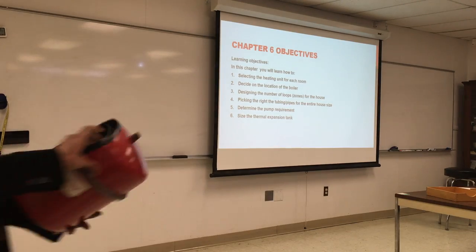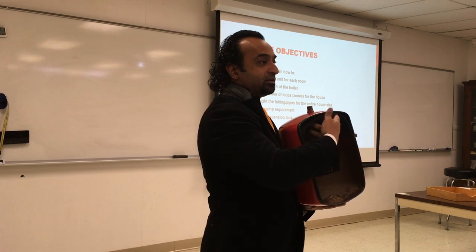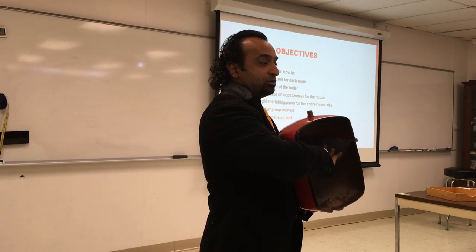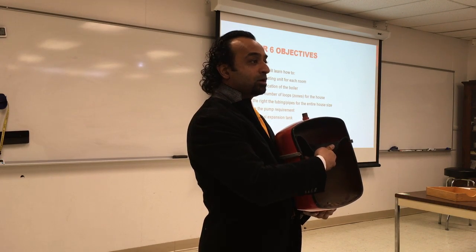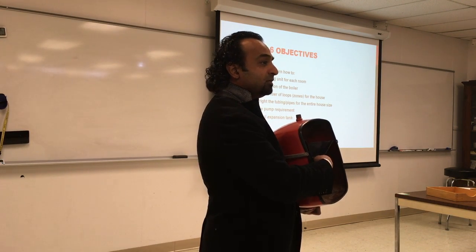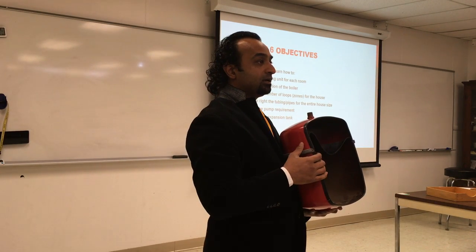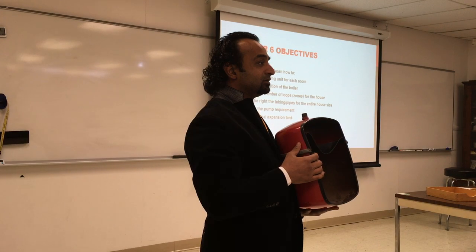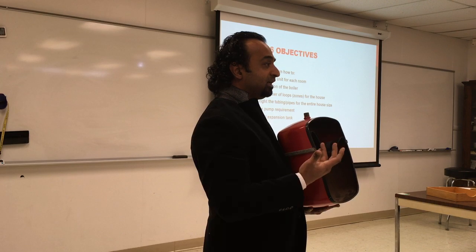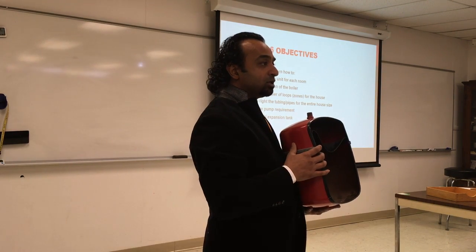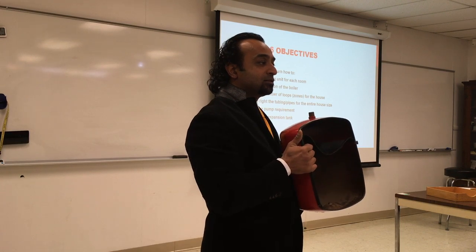So this is a thermal expansion tank. If you see, it has a membrane in it. So the water goes into the top, and this will provide some kind of pressure to keep the water under the right pressure in the system. Water, as it gets heated, what happens to it? It expands. If there is no room for expansion, it might leak, it might ruin some pipes. So it's very, very essential to know what is the proper size thermal expansion tank.